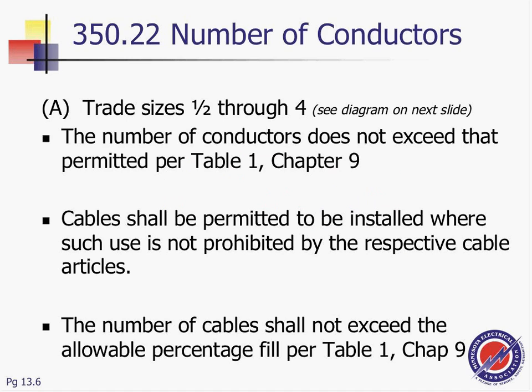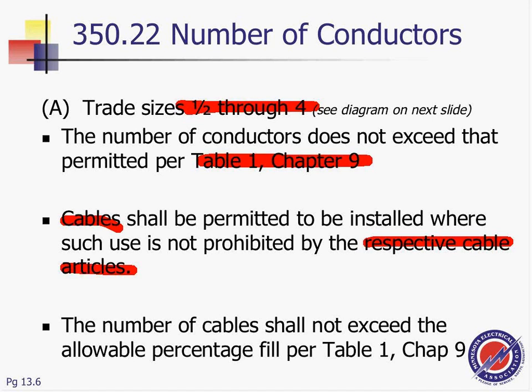Now conductors. Conductors, guys, from 3/8 all the way to 4, you're going to go to Table 1 of Chapter 9, and Annex C. Annex C will tell you, if all the conductors are the same, how many conductors can fit in the Liquidtight flexible metallic conduit. Can I install a cable in this? Bring it on, as long as the cable article does not prohibit the cable from being installed in it. For example, can I install an NM cable in a Liquidtight flexible metallic conduit? Bring it on, Kevin, no problem. Can I install an SE cable? No problem, as long as the article allows you to do so.